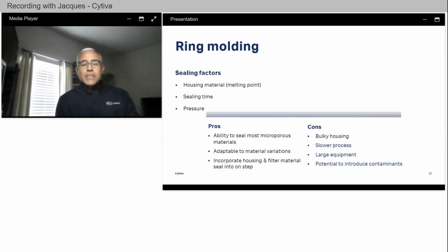The advantages of insert molding include the ability to seal most microporous materials. There's better adaptability to membrane thickness variations. It can incorporate sealing of both halves of the device housing and membrane in one step, as well as improving the robustness of a device so that it can withstand high-pressure processing applications.